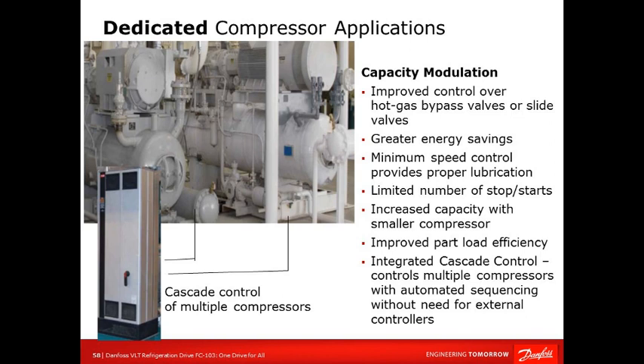We do have dedicated compressor application functionality built into the drive. Some things you can monitor, obviously, is minimum speed control, because we worry about lubrication. There's integrated cascade control, for example if there are multiple compressors, there can be automated sequencing as compressors come on. It's a built-in soft start in the VFD for the compressor application. So again, a lot of flexibility. We're trying to improve the overall efficiency of the system, but also utilize the intelligence in the drive to make it easy to work with for your applications.